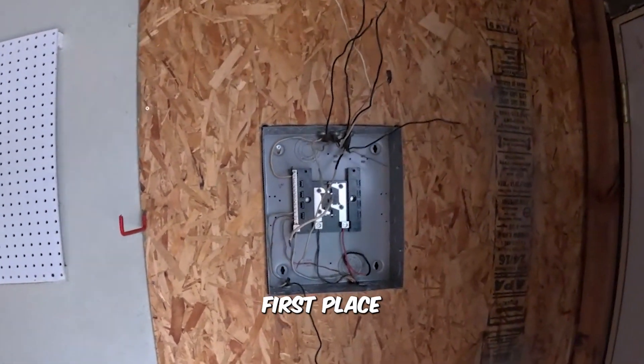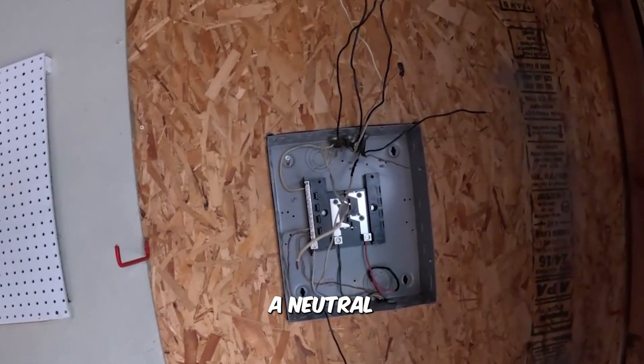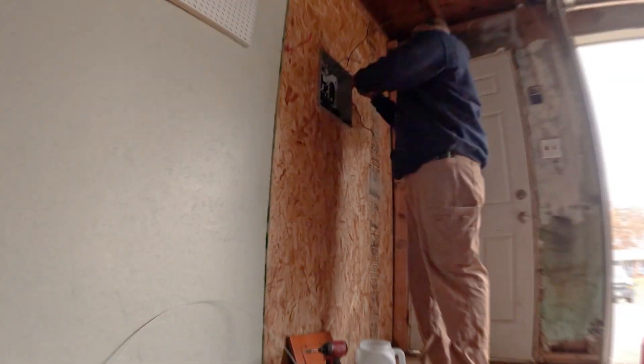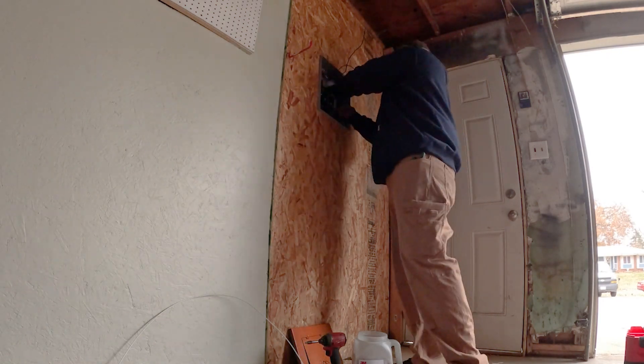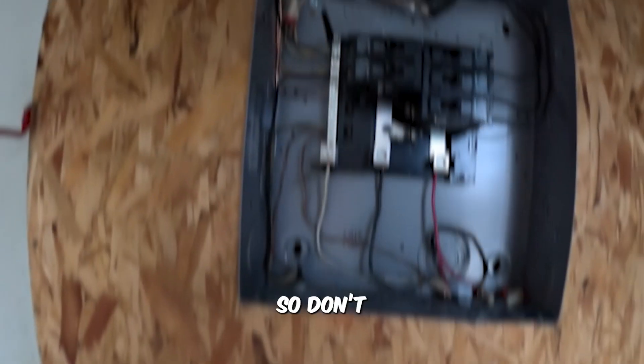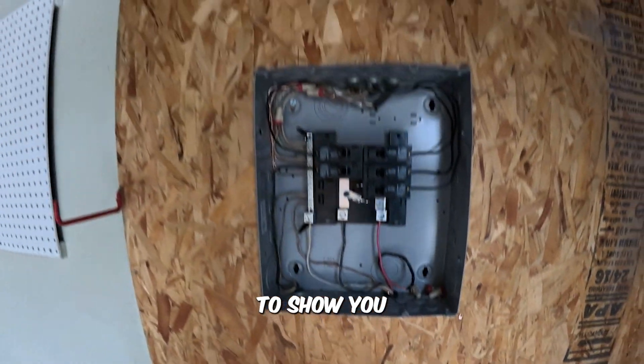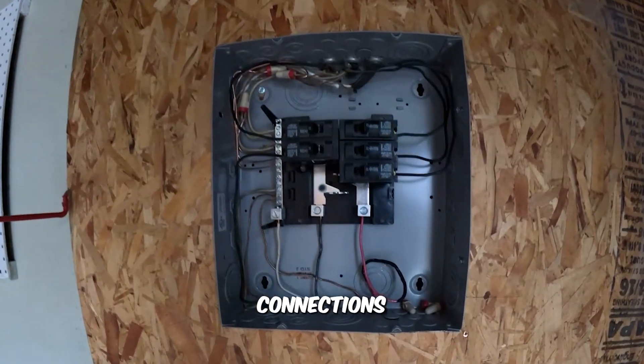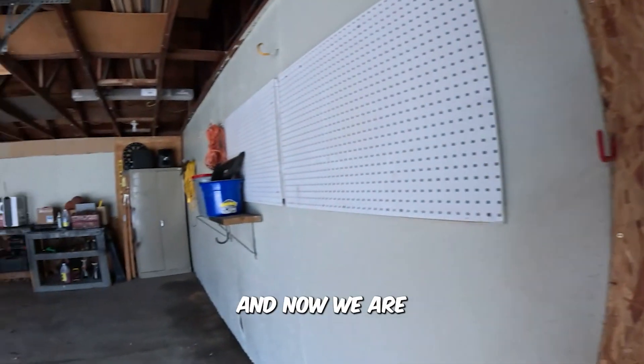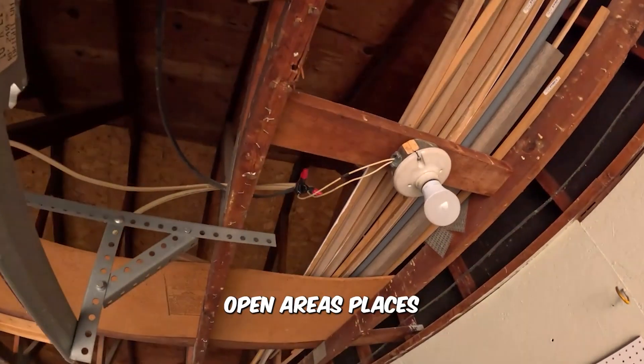We got it reconnected right. We're going to make it an actual true single phase coming in here now, and we got a neutral hooked up. Once we get this fired up and running it'll be appropriate. We ended up making the connections right, made it look pretty, and now we are on the precipice of going through and fixing all these open air splices.